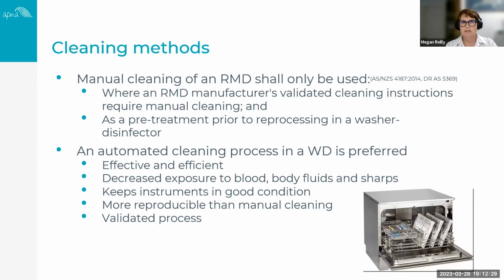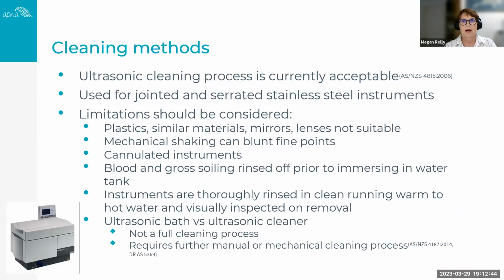So it's effective, it's efficient. It certainly decreases your risk of exposure to blood and body fluids and sharps. It keeps the instruments in good condition. It's far more reproducible than manual cleaning, and it is a validated process. However, under the current standard, the ultrasonic cleaning process is acceptable. And ultrasonic cleaning tends to be used for jointed and serrated stainless steel instruments.